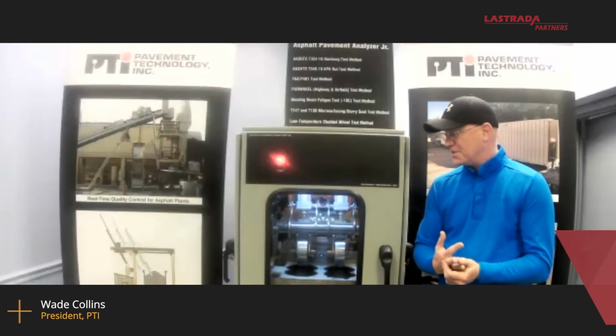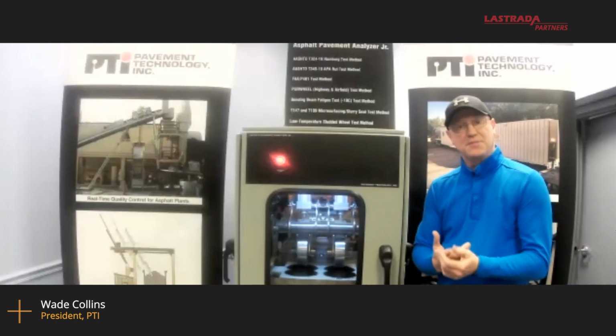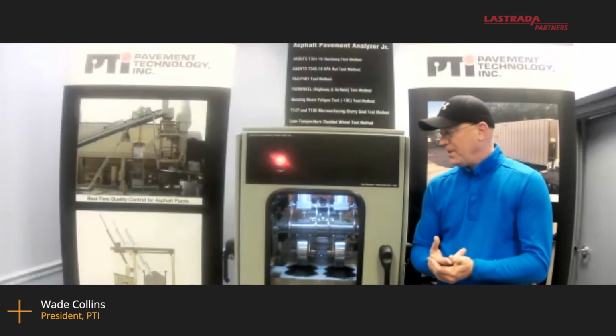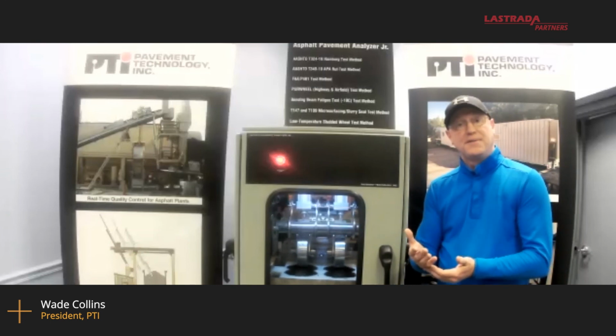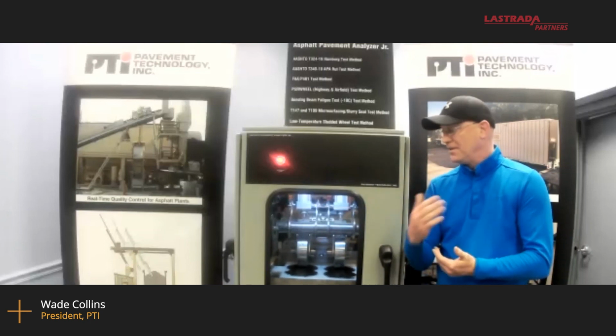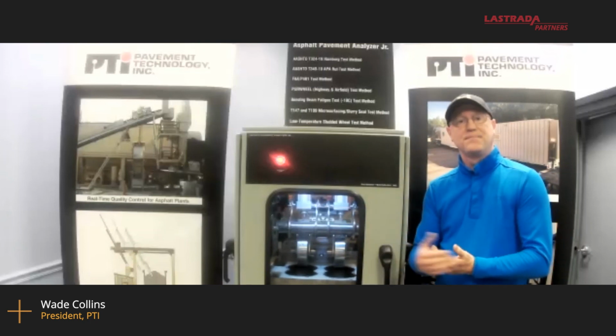For calibration, we recommend that the wheel load be calibrated periodically. We also recommend that the air and water temperature be calibrated, and the speed and then the linear variable displacement transducers. We do offer a calibration kit that a customer can purchase with a machine, or later if they'd like to, and they can do all of those calibrations.